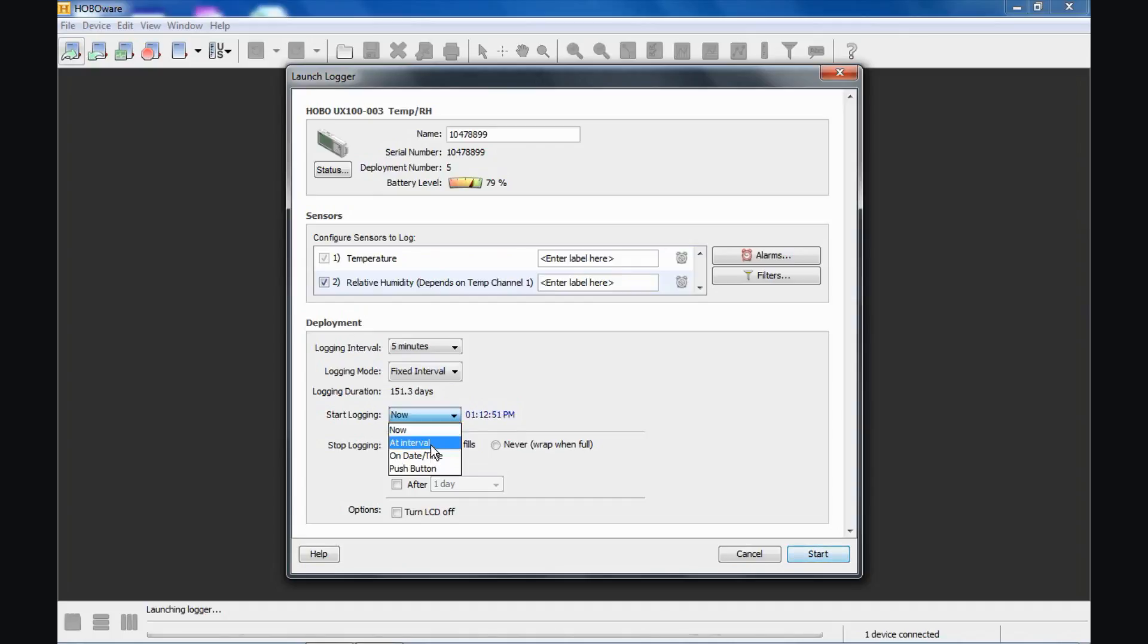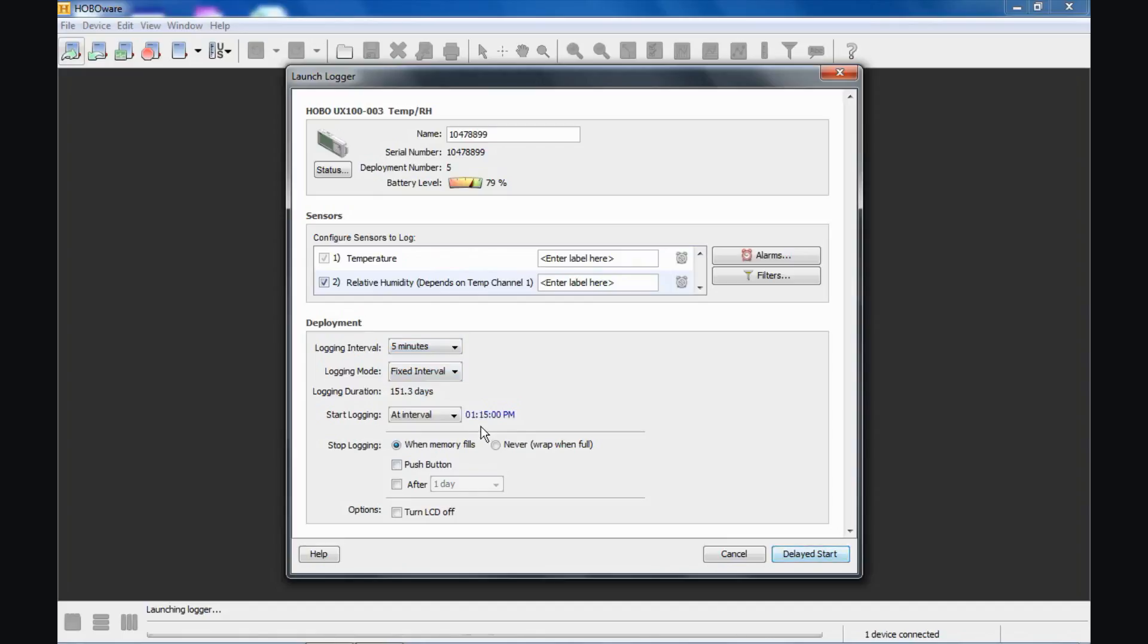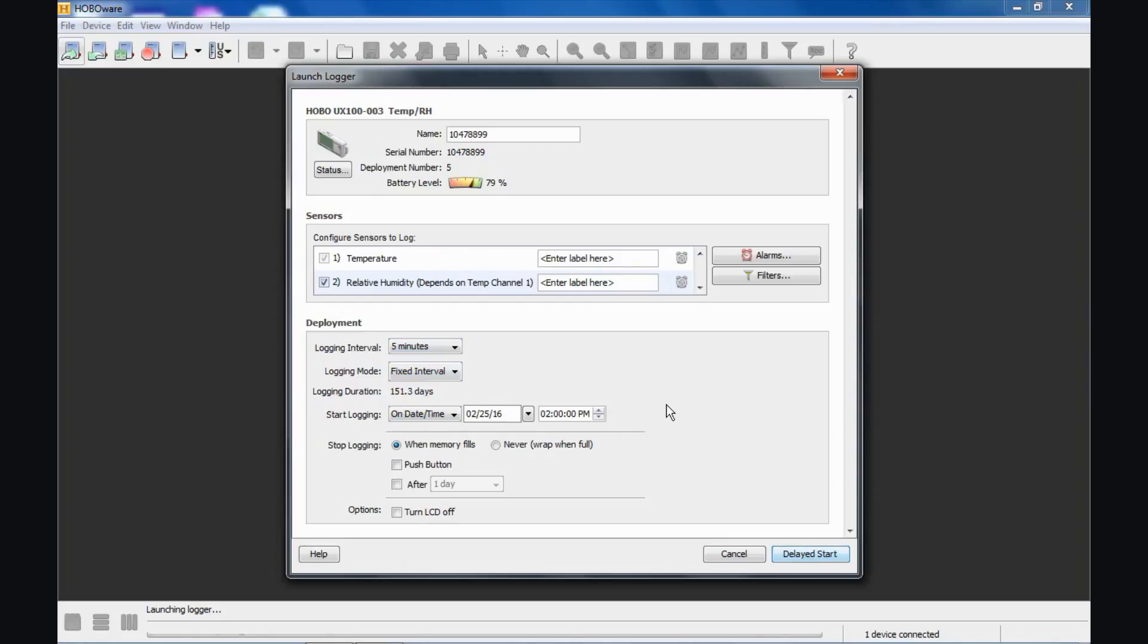If we select at interval, notice what happens to my clock. It should change to the next five minute increment because we're saying we want it to start on a five minute increment. If we change this to ten minutes, this would be a ten minute increment. Hourly, it would be an hourly increment. On date and time gives you the ability to program a future time and date when you want the logger to automatically begin logging. This can be set up to six months in advance. This is a good feature to take advantage of if you have multiple data loggers that you are configuring and launching and you want them all to start at the same time.